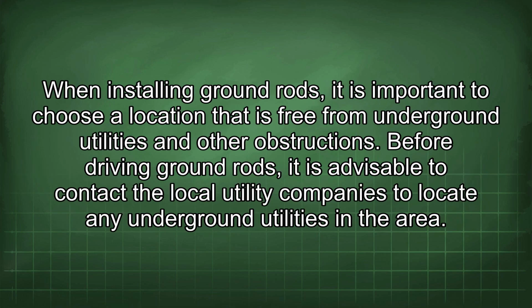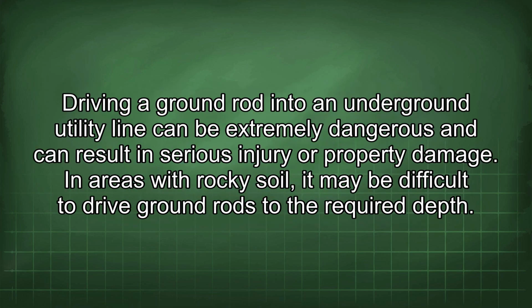When installing ground rods, it is important to choose a location that is free from underground utilities and other obstructions. Before driving ground rods, it is advisable to contact the local utility companies to locate any underground utilities in the area. Driving a ground rod into an underground utility line can be extremely dangerous and can result in serious injury or property damage. In areas with rocky soil, it may be difficult to drive ground rods to the required depth.